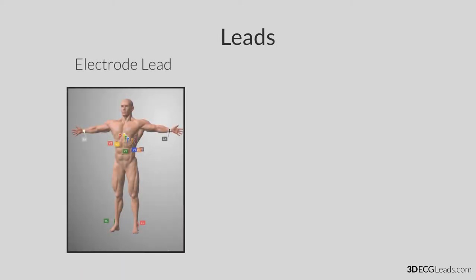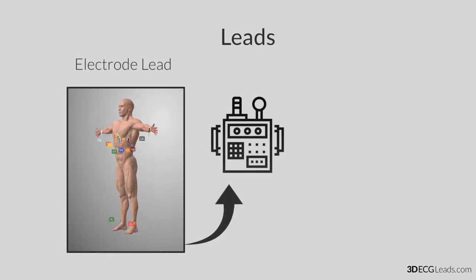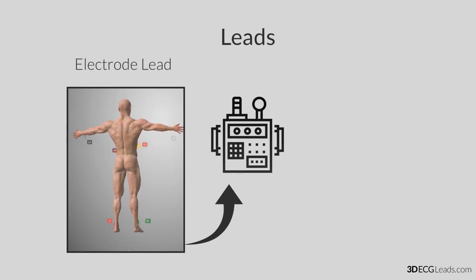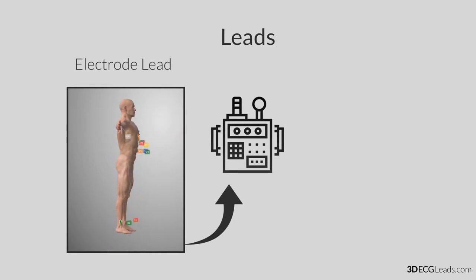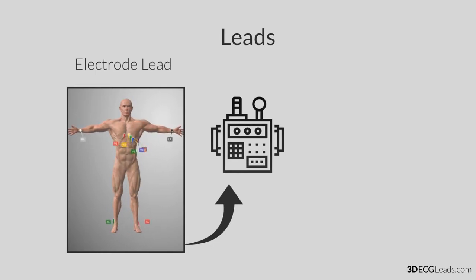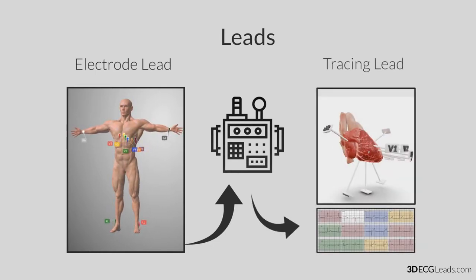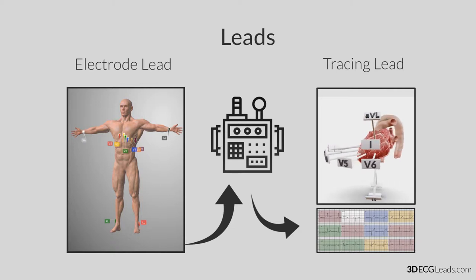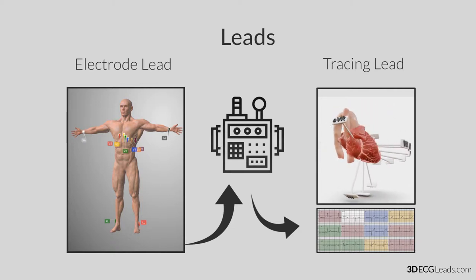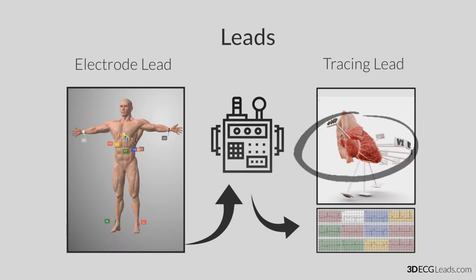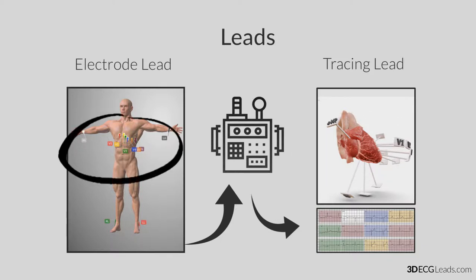An ECG lead can refer to the wired connection that goes from the skin electrode to the machine — we will refer to this as electrode leads. Secondly, the lead can also refer to the tracing that is recorded by the ECG machine — we will refer to this as tracing leads. So to clarify, when we say a 12-lead ECG has 10 leads, what we really mean is that a 12-lead ECG tracing is recorded by 10 skin electrodes.